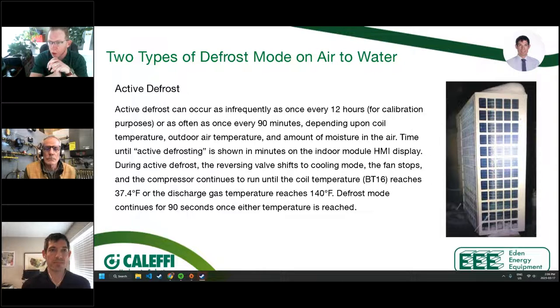The other thing that we'll caution, and we all know this, but I just want to say it out loud, is that every manufacturer has a different defrost cycle. So if you were to look at SpacePak, IBC, and the Advantage unit, all three of them utilize different methods for defrost. So don't just assume that the buffer tank is how your defrost cycle is being used. In the case of the Advantage unit, it actually has all the defrost logic built into that indoor unit. You don't need a buffer tank to do defrost. It doesn't even use it. You need to know that.